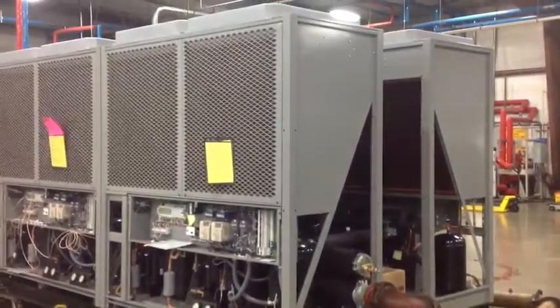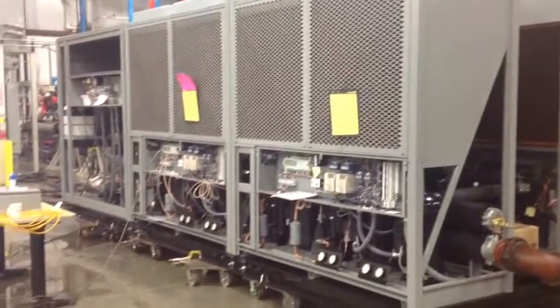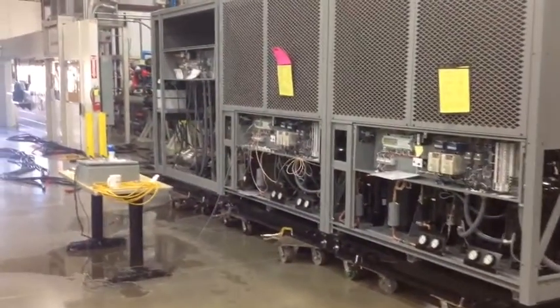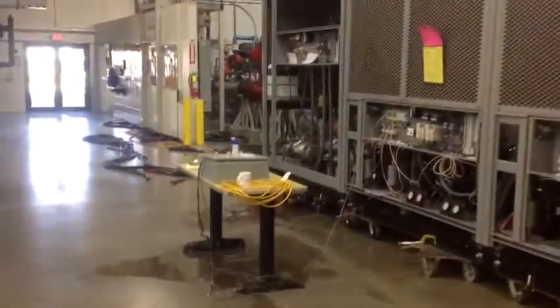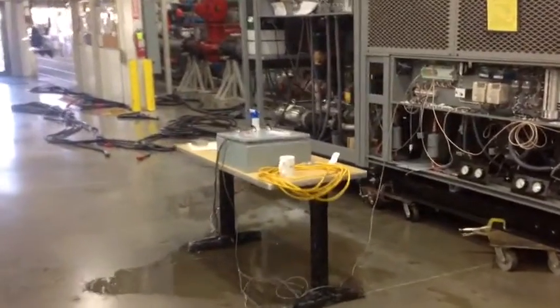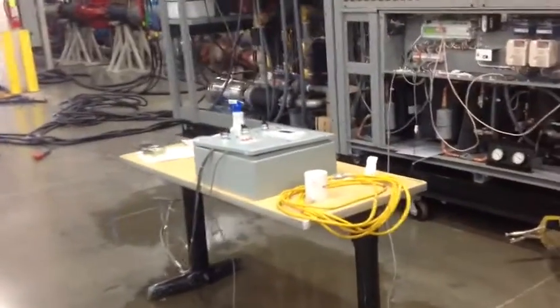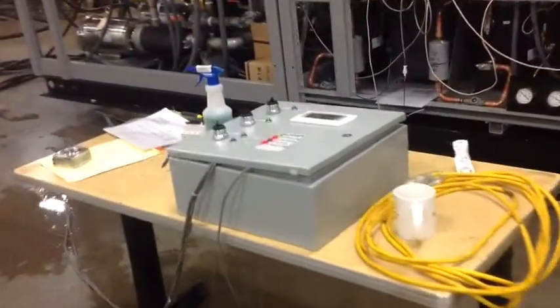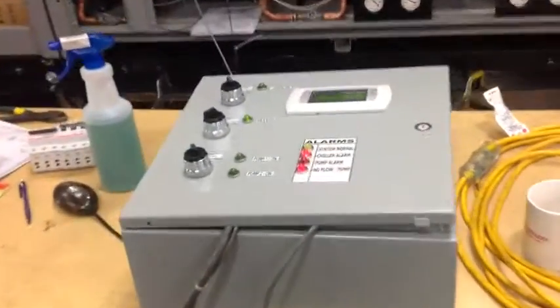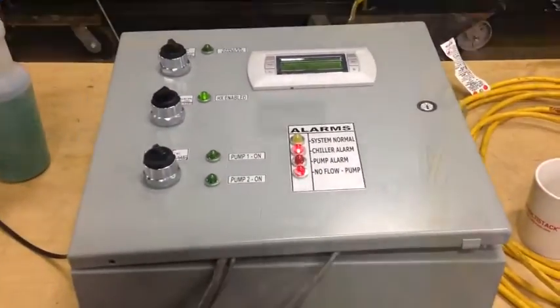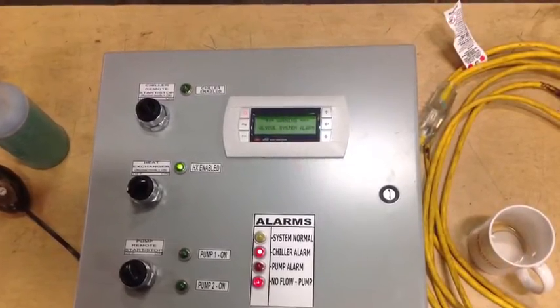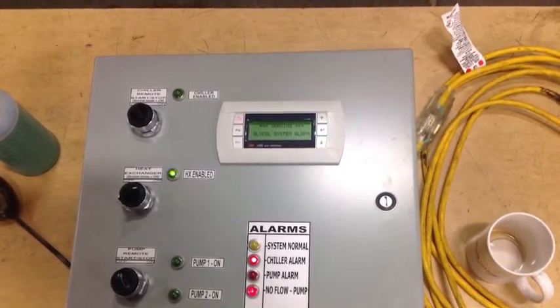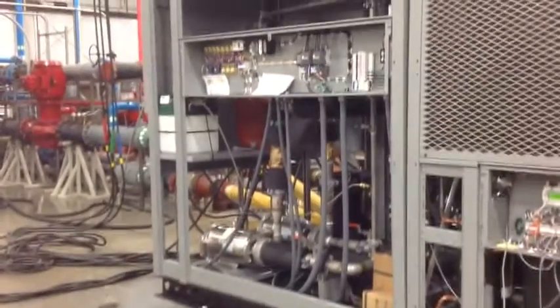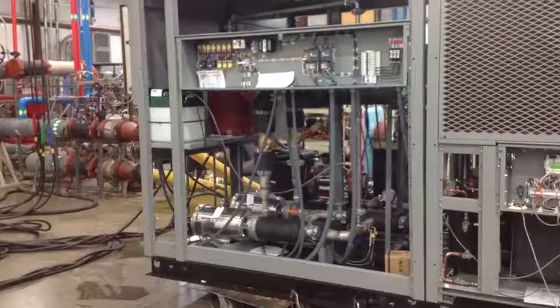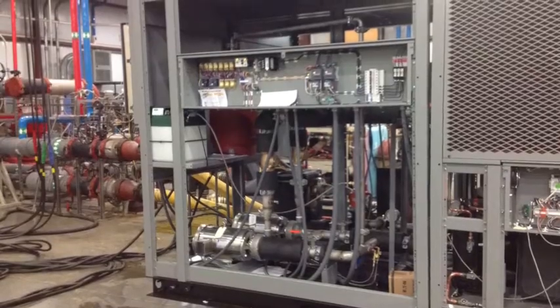And now panning back to see the front of the array. And down on the left you can see the pump module. As we move down toward the pump module, we'll see the remote panel. Again, this is mounted in the space, and its interface point on the array is the C1 panel. You can see various LED lights, the pump 1, pump 2 start-stop, the heat exchanger enabled indicator, and the remote display itself, which is a mimic of the master controller.